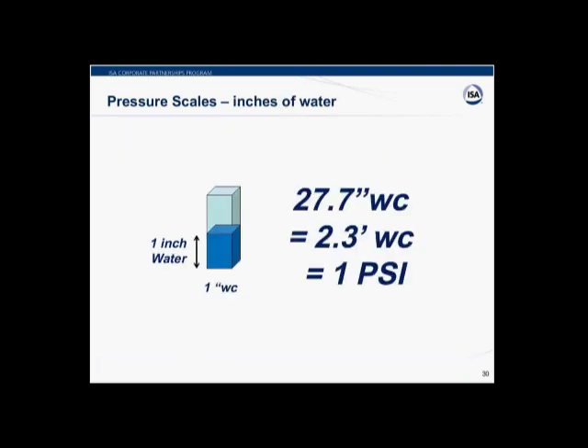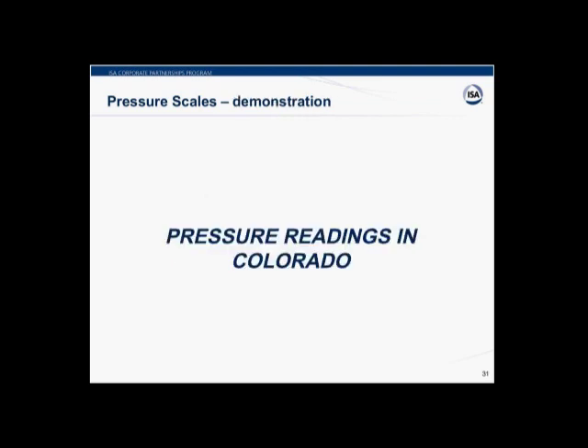The last scale Hunter covers is inches of water column, a unit very common in the US but not used in most metric countries (where WC means water closet in Europe). An inch of water is the weight of a one-by-one-by-one-inch cube of water. For reference, 27.7 inches of water equals 2.3 feet of water, which equals 1 PSI. Hunter then turns it over to Roy for a live demonstration.